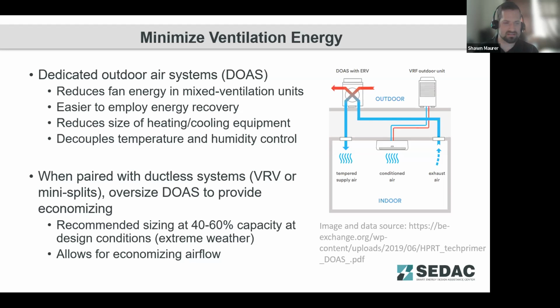When paired with ductless systems, there is a recommendation to oversize dedicated outdoor air systems a little bit so that you can provide economizing airflow. The recommendation is 40 to 60% of your dedicated outdoor air system's capacity at your design extreme weather conditions. And then when you're in mild conditions, you can get free outdoor air ventilation. You can throw that thing open, pump as much free cooling into the building as you want during economizing periods. It's actually a common practice for a lot of net zero buildings.